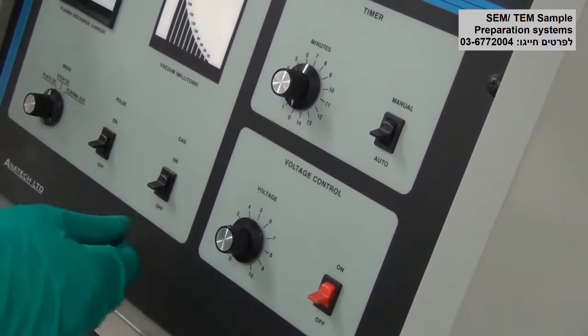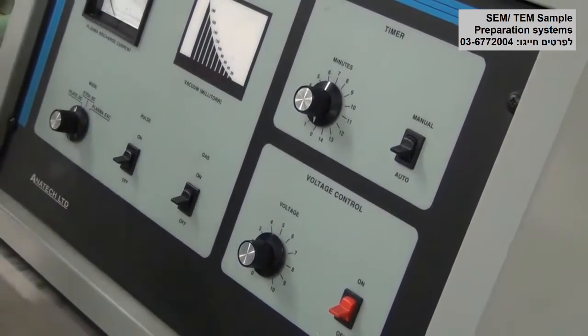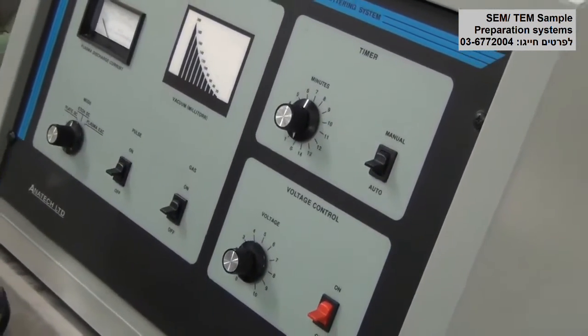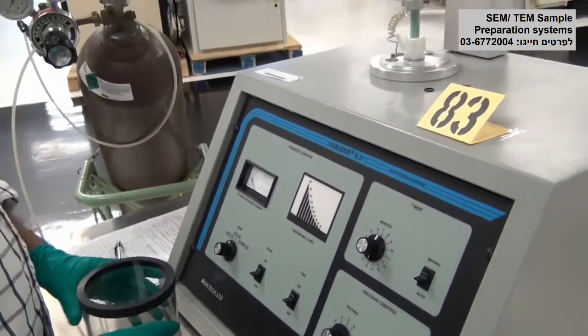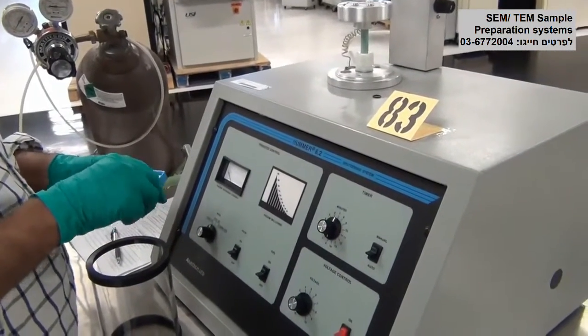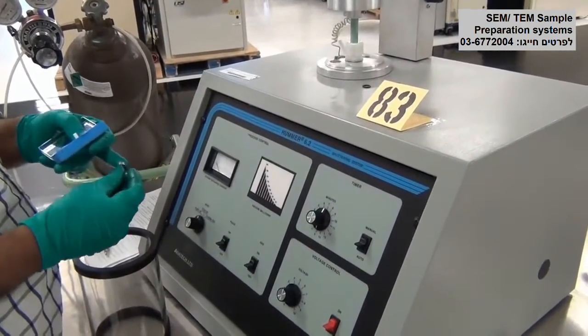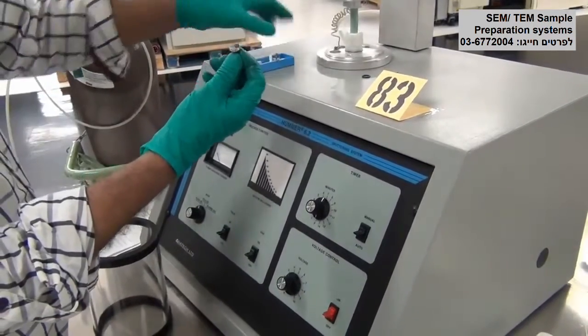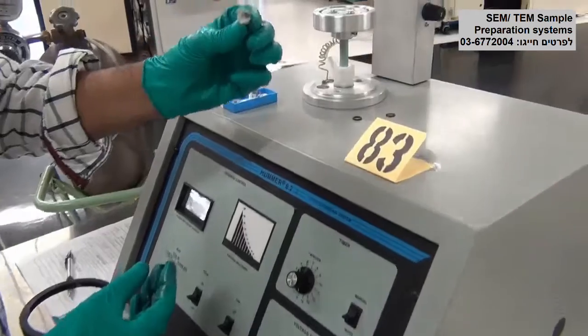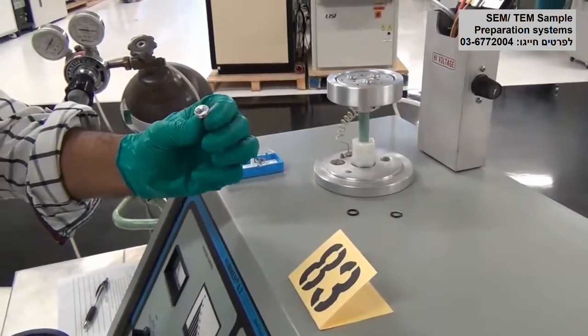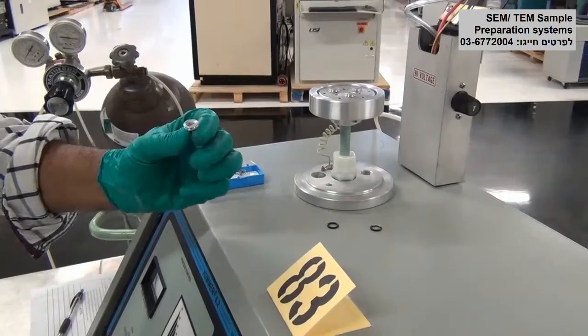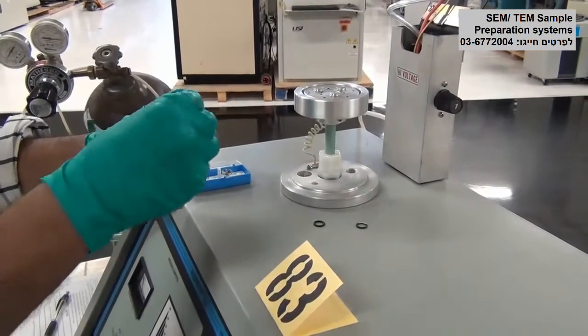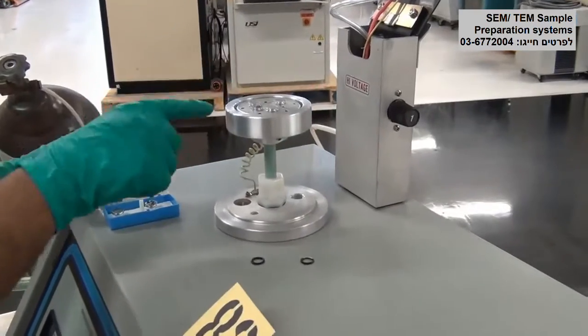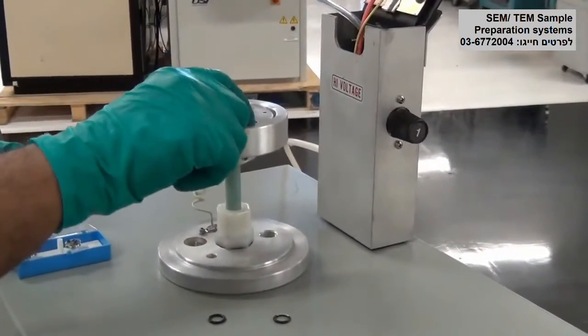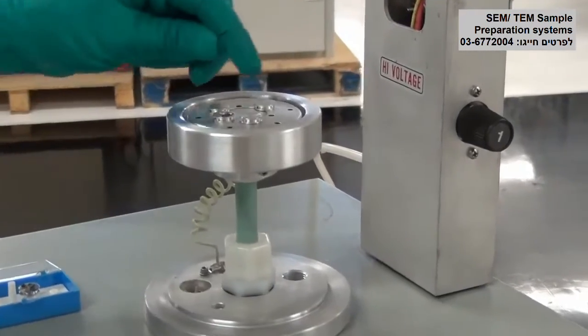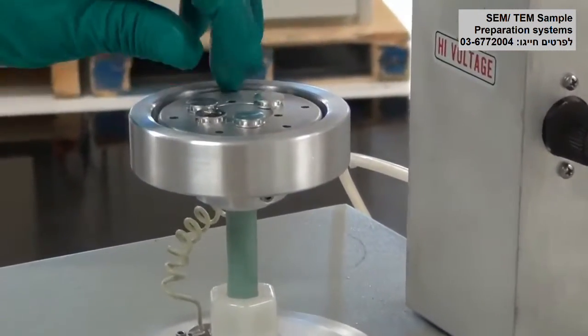But the system has a built-in gas valve to turn on the gas. I hooked it up with argon gas, and this system is basically used for coating scanning electron microscope samples mounted on a sample holder like this. You can use silver paste or double-sided conductive tape. And this sample holder, several sample holders can be placed on the sample holder. I have here about 4 of them. We can put as many as we need.